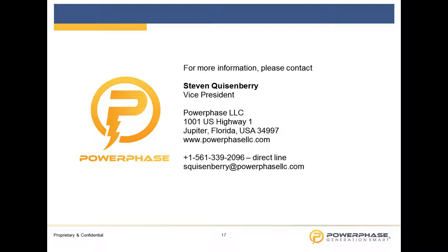Yes, it's a good question. As I mentioned in the presentation, we make a constant amount of air. The way we've designed our Turbophase module is our compressor has inlet guide vanes to open up to support changing ambient temperatures, and our engine has turbochargers on it, which allows us to keep a constant horsepower. By keeping horsepower constant and the mass flow constant to our compressor, we make the same air. That same pound per second or kilogram per second of air makes the same number of kilowatts in your gas turbine. So we are constant across ambient temperatures, constant across humidity, and constant across elevation.